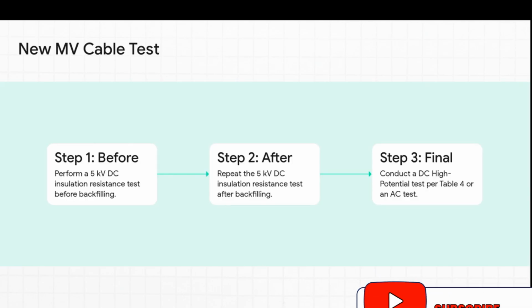So you've laid your brand new medium voltage cable. Great! Are you done? Not even close. You have to test it, and the sequence is everything. First, you run an insulation test before you bury it. Then you bury it, and you run the exact same test again. And only then do you do the final high voltage test, the hipot test. It's a step-by-step process to make sure that cable is perfect.